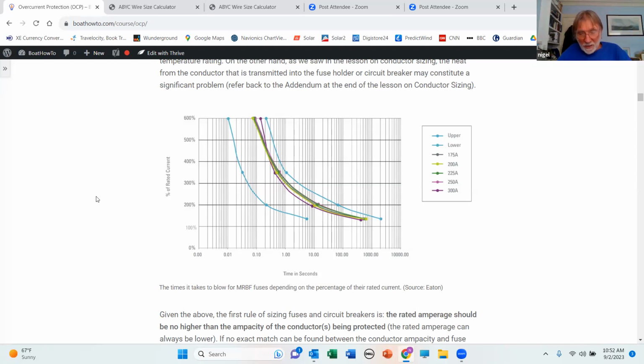There are some devices like sensitive electronics. If we're going to protect them with a fuse at the device, we want a fast blow fuse that's going to blow the moment it sees anything over the rated amperage of the fuse. But typically speaking, we want fairly slow blow fuses and circuit breakers. There are 2 circuits on the boat where we're not required to put overcurrent protection. One is a temperature sensor. So if you strap a temperature sensor to your battery post, it doesn't need overcurrent protection. And the other one is a cranking circuit.